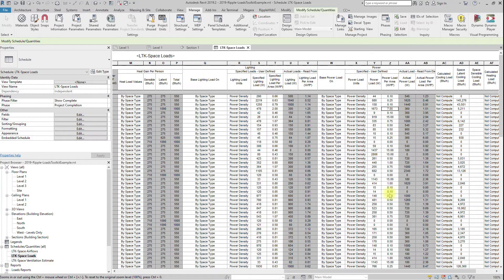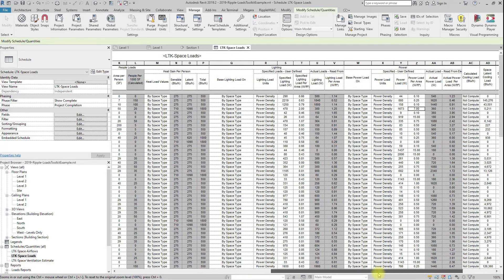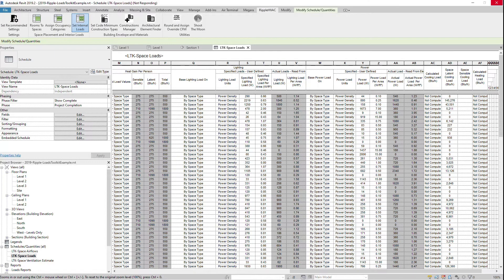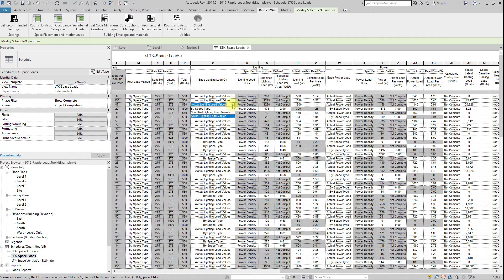Run the Internal Loads button. This button will compare the actual internal load values with the space type default values, and if the actual internal loads are at least 75% of the space type default, it will use the actual value by setting the base load on parameter to actual.